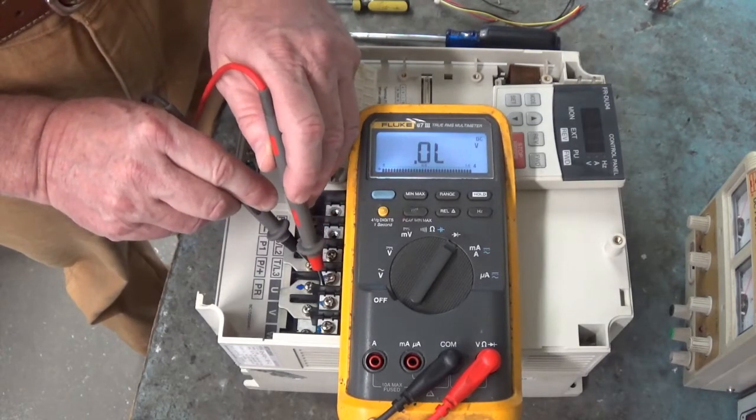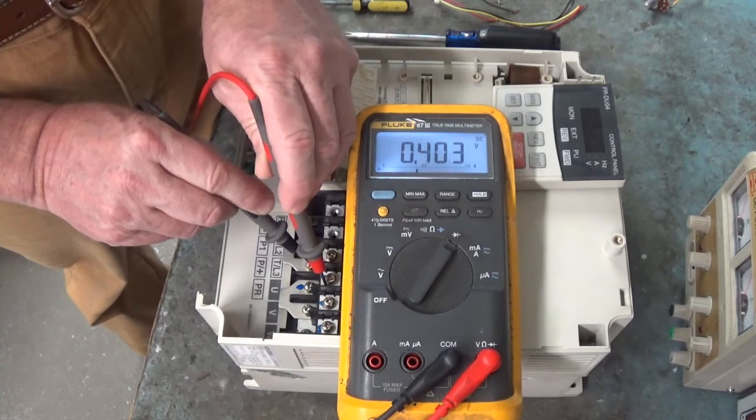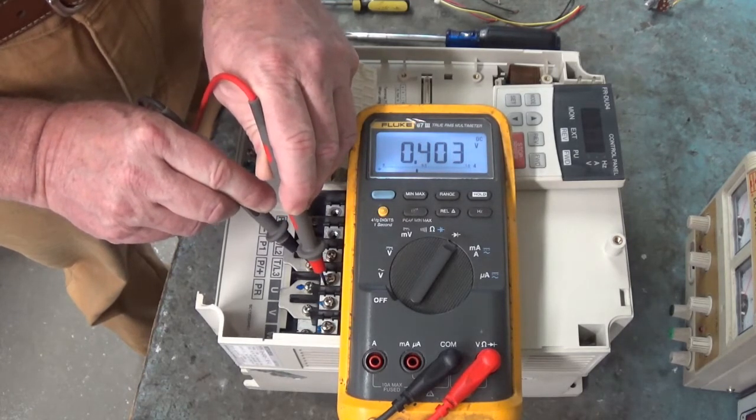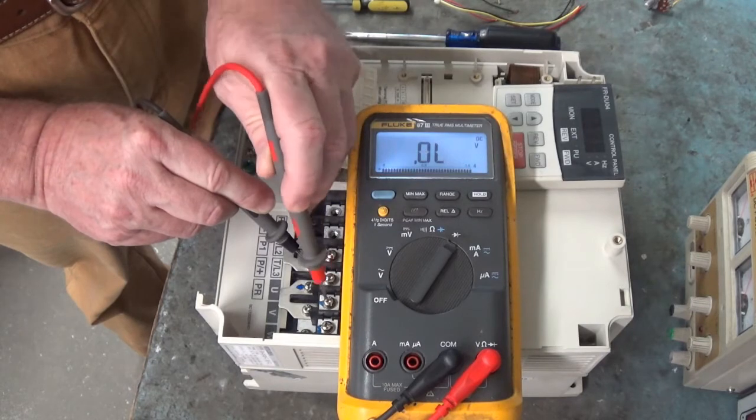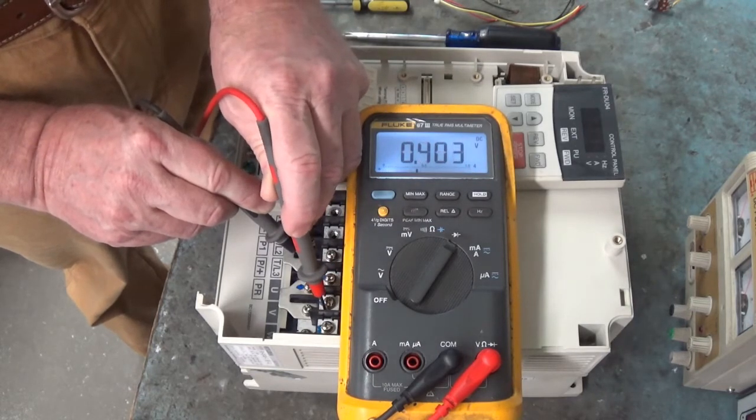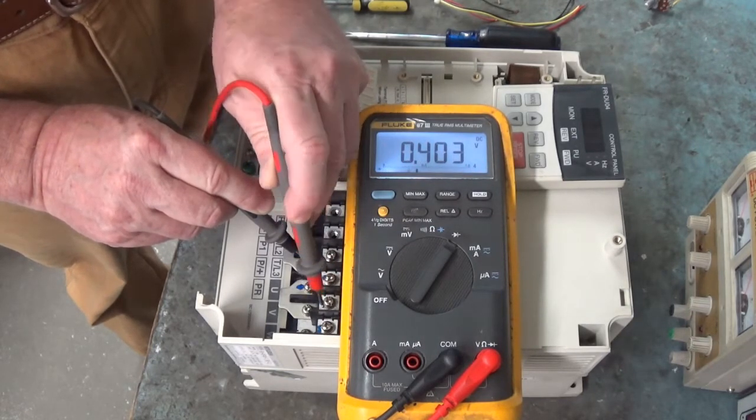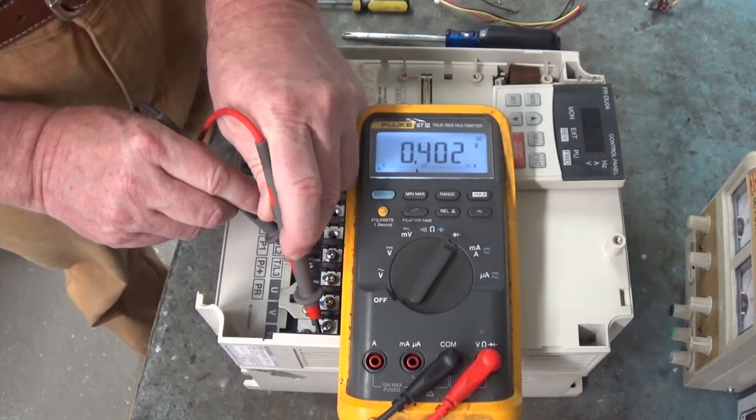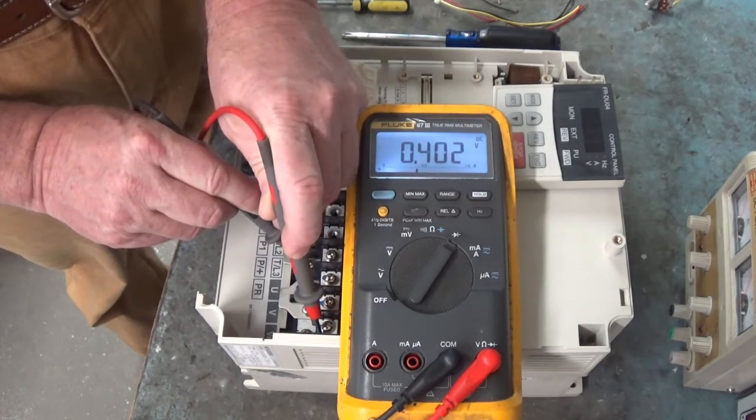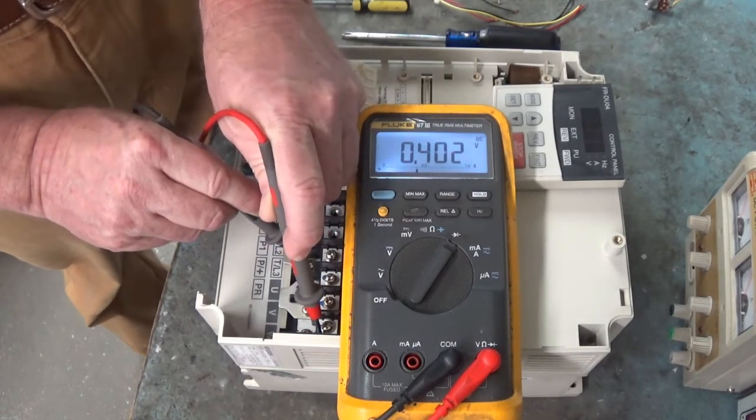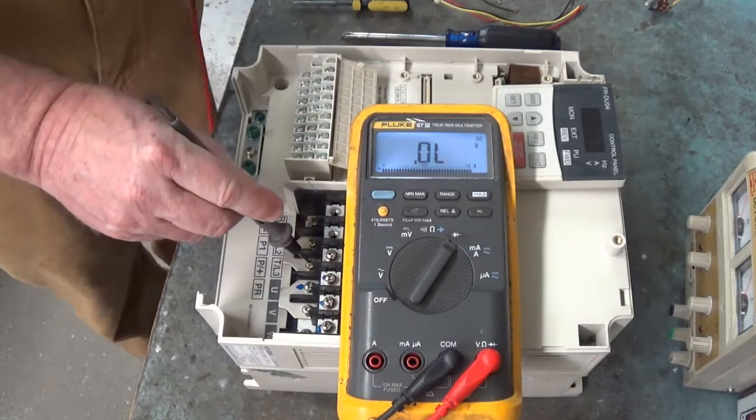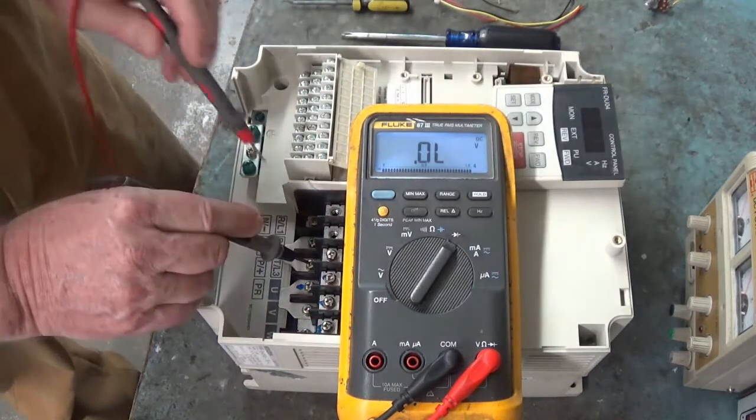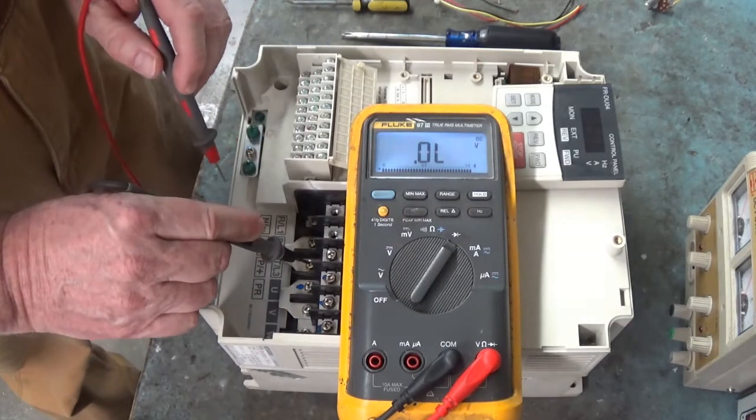Let's go to U with the red lead. 0.403. V with the red lead. 0.403. W with the red lead. 0.402. Our power module to run the motor is good.